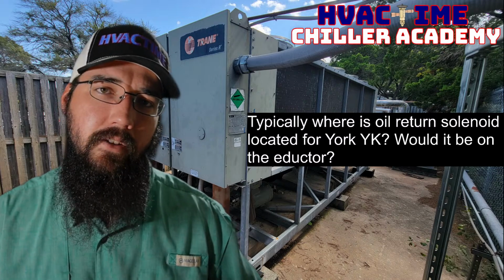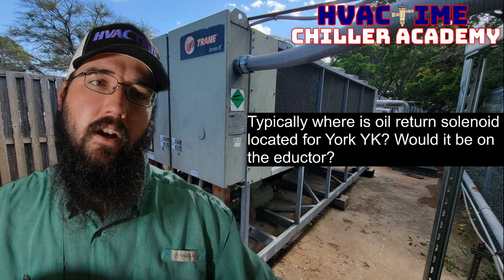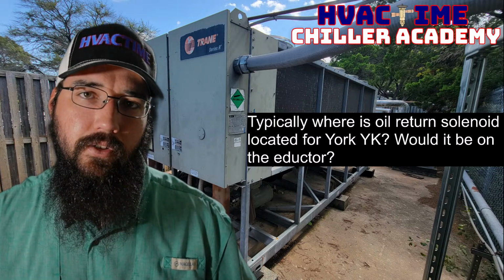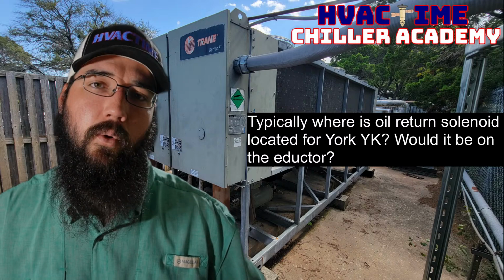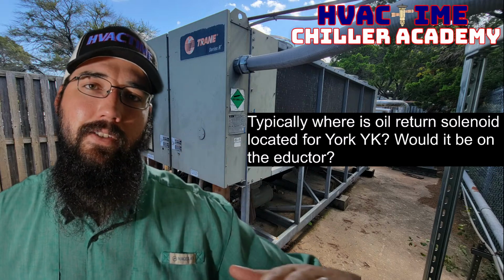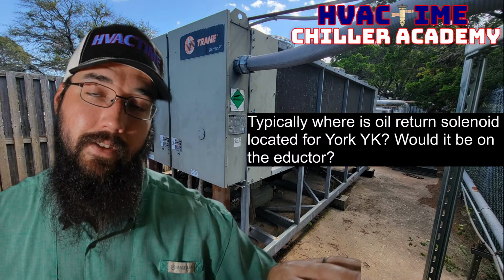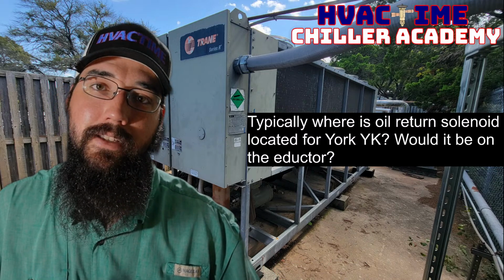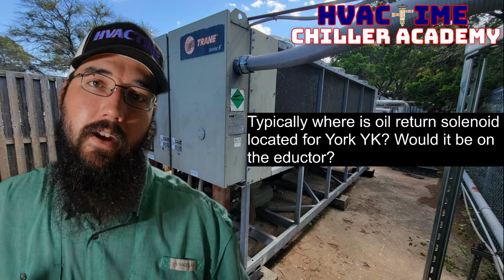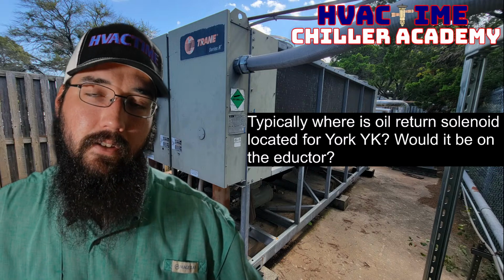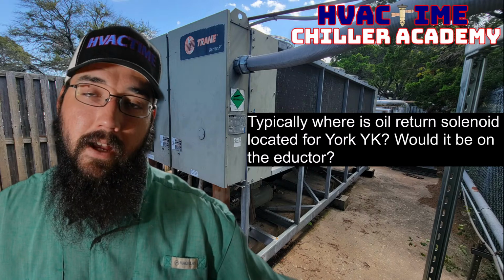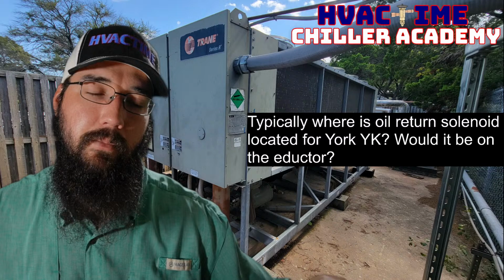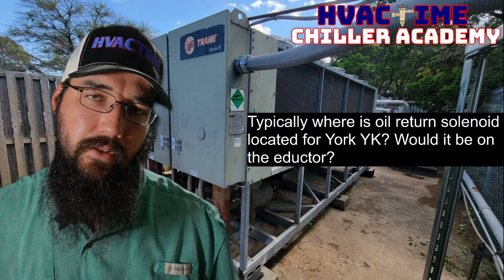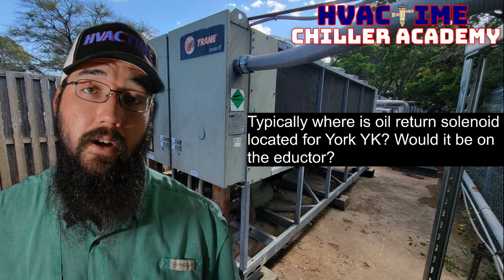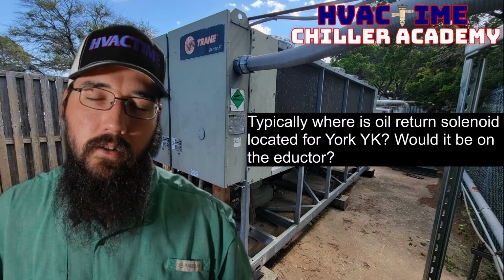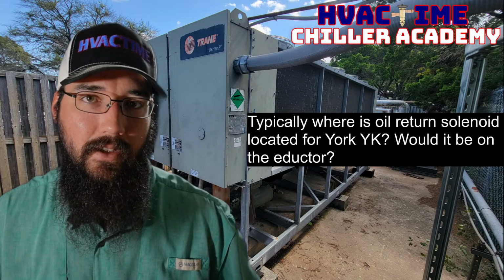But then you add it getting oil logged because you're not getting up to where that eductor port is, then you could start causing even more issues with oil logging. So with a YK, you're going to set the liquid level set point based off the condenser level, but you have to pay attention to what that means on your evaporator side and where the liquid level is in the evaporator. And so these things have to have a bit of a balance. I've talked heavily in the past through other means about how we need to set the condenser levels on our YKs for proper operation, but we cannot ignore where the evaporator level is in that process. These two go hand in hand.